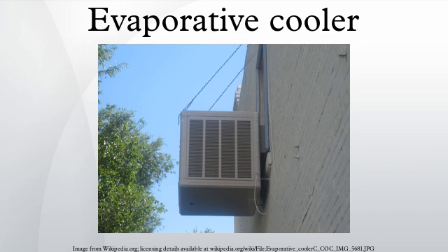Less expensive to operate. Estimated cost of operation is 1/8 that of refrigerated air. Power consumption is limited to the fan and water pump. Because the water vapor is not recycled, there is no compressor that consumes most of the power in closed-cycle refrigeration. The refrigerant is water. No special refrigerants, such as ammonia, sulfur dioxide or CFCs, are used that could be toxic, expensive to replace, contribute to ozone depletion and/or be subject to stringent licensing and environmental regulations.